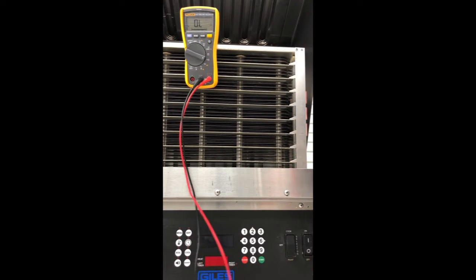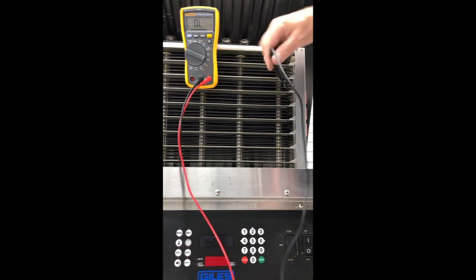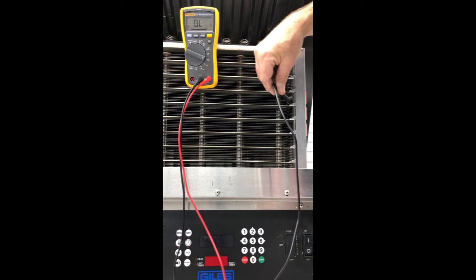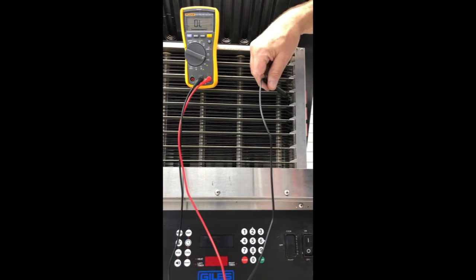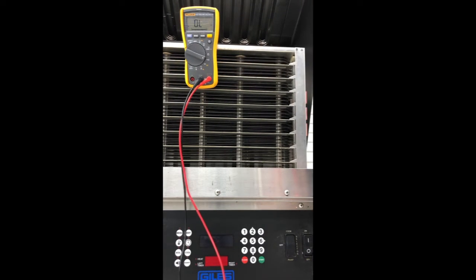Most of the time, if you look at this center contact on the back side, you'll notice there is a small copper tab that extends from it. It goes to an aluminum bar right here, and this aluminum bar is what the wires are attached to. So if you go from the contact, copper, to aluminum to the wires, it should read like one solid lead, just like that. If it does not see those wires from that contact, you're going to get a wash light every single time. You'll never be able to get out of the alarm.